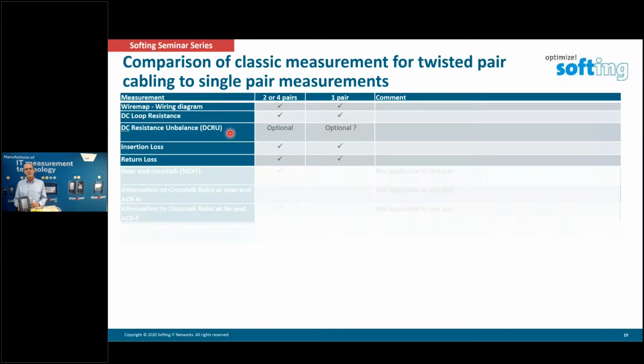If you remember a previous webinar we did on DC resistance unbalance, that's a new measurement for 2 and 4 pair cabling. It's really important for high power PoE, 4 pair PoE applications up to 90 watts. This measurement measures not only the loop resistance of a cable, but also single wire resistance.